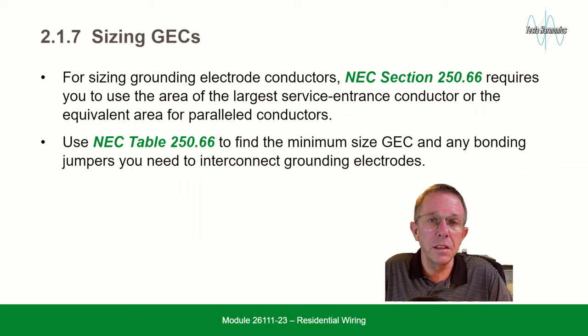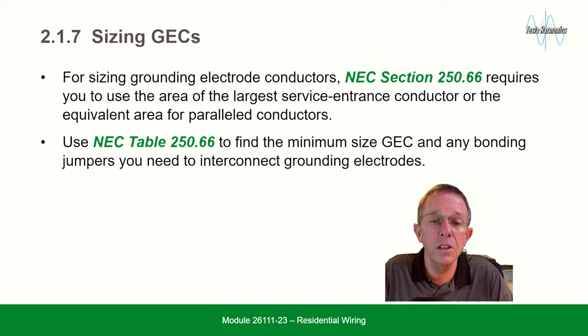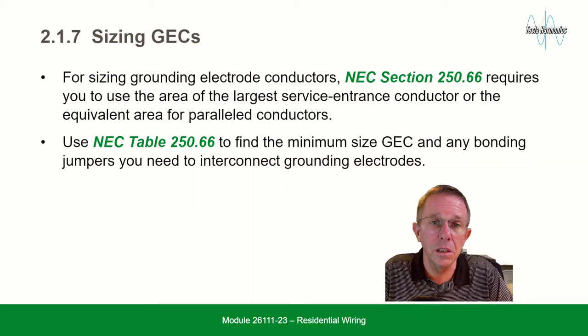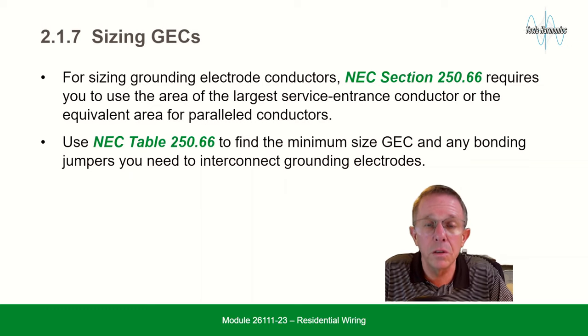Sizing GECs: for sizing grounding electrode conductors, NEC section 250.66 requires you to use the area of the largest service entrance conductor or the equivalent area for parallel conductors. Use NEC table 250.66 to find the minimum size GEC and any bonding jumpers needed to interconnect grounding electrodes.